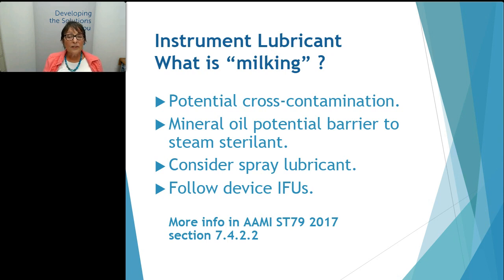This is very inappropriate. It's a great avenue for cross-contamination, actually creating another biofilm farm with your lubricant. Mineral oil itself can be a potential barrier to steam sterilant, and it can get sticky and build up in the box locks. Do look at your IFUs. Many still refer to mineral oil as the preferred lubricant, but be careful not to over-apply it, and you might consider a spray instead of a dip-type bath.